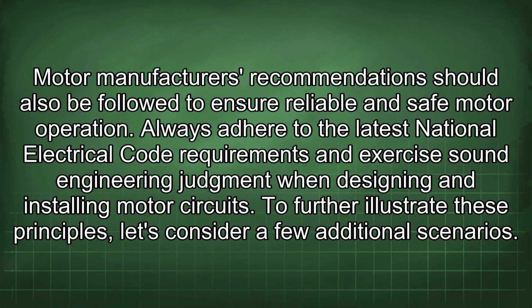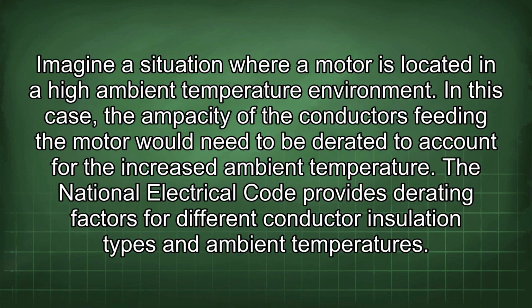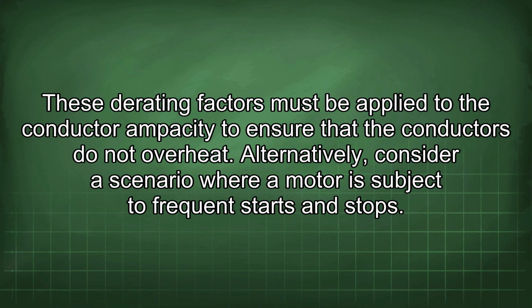To further illustrate these principles, let's consider a few additional scenarios. Imagine a situation where a motor is located in a high ambient temperature environment. In this case, the ampacity of the conductors feeding the motor would need to be derated to account for the increased ambient temperature. The National Electrical Code provides derating factors for different conductor insulation types and ambient temperatures. These derating factors must be applied to the conductor ampacity to ensure that the conductors do not overheat.